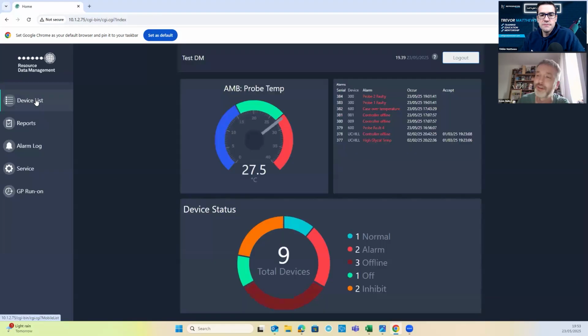I'm not signing off on anything I've commissioned unless I've seen it run overnight. Because what always happens is it works perfectly when you're watching it, and then you leave it alone for 20 minutes, a bit of dirt comes down the pipe, wedges in the valve, and it doesn't do a defrost. And then they shout at you when it's iced up. So that's where I am with those.